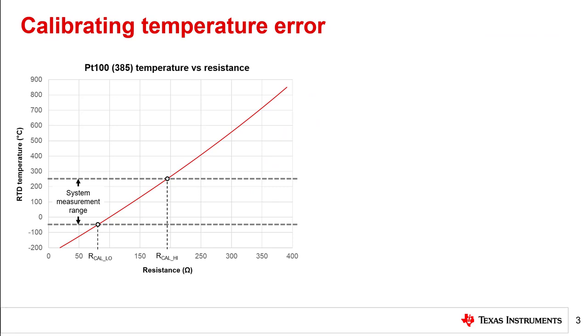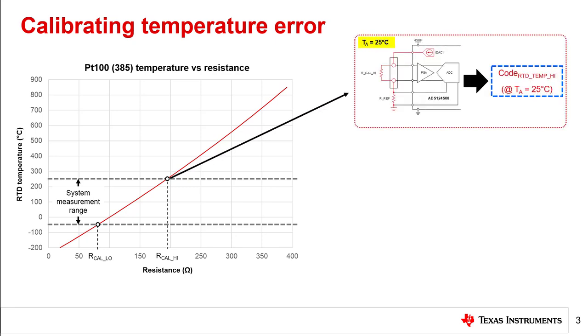As an example, let's recall the PT100 temperature versus resistance curve used throughout this module series, shown on the left. As stated previously, only two calibration resistors are needed as long as we just need to calibrate this specific RTD type. To calibrate, first perform an initial error calibration at the initial error temperature, typically 25 degrees Celsius. This was described in the previous Precision Labs module and is shown for RCAL high in the red box in the system on the top right.